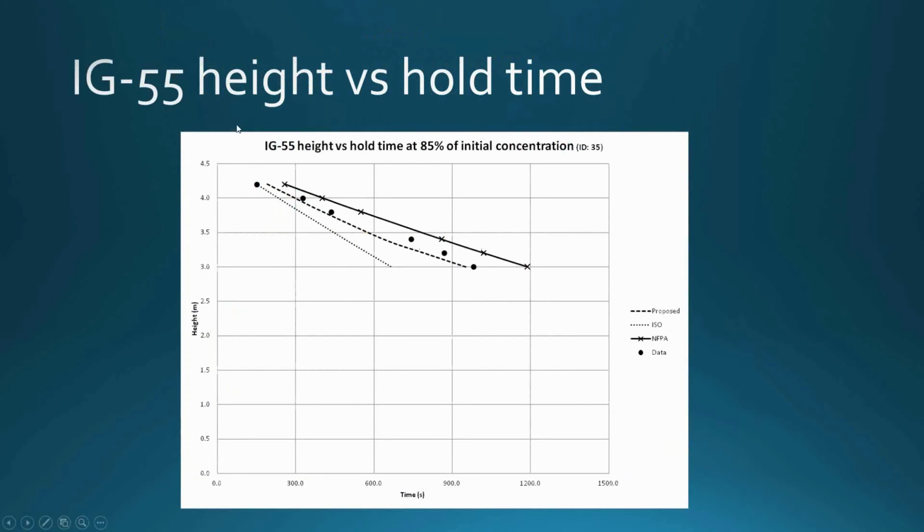So here is IG55 hold time versus height. This is the data that we got. This is the NFPA, which is a little bit optimistic. And this is the existing ISO formulas, which are a little conservative.